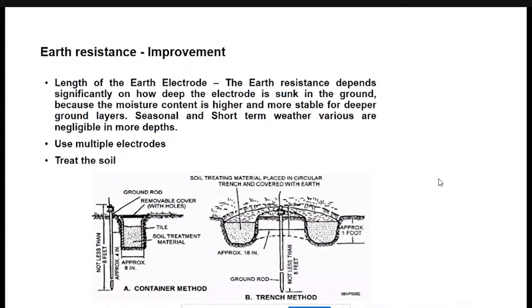When it comes to earthing, many places still practice using a GI pipe with salt and charcoal. This is a wrong method we have been following. Whenever you use a GI pipe with salt and charcoal, remember the salt and charcoal should not be provided along with the electrode in the same pit. The electrode should be separate, and salt and charcoal should be provided in a trench around the electrode.